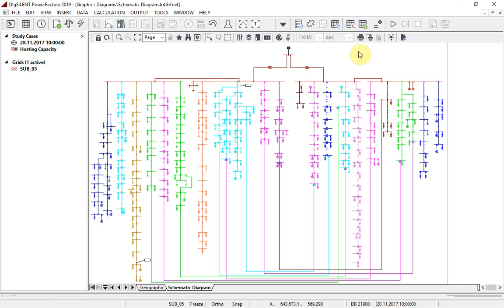For the analysis of distribution networks in particular, the new hosting capacity tool calculates the amount of generation or consumption that can be connected to the grid without any network expansion, whilst not violating any system constraints.